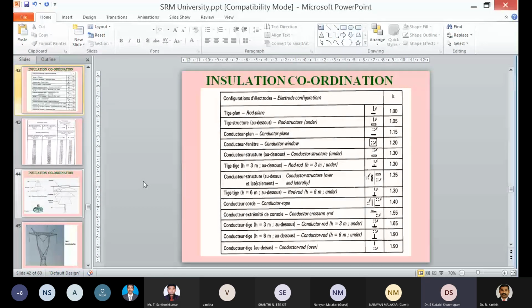So I have just shown an insulation configuration for calculation purposes. For a rod plane configuration, K is nothing but the factor by which we multiply. This is known as the safety factor in insulation design. In the next slide, I will explain, for different configurations, that is rod plane, rod conductor window, conductor plane, what safety factor we will consider. With respect to this factor, your insulation distance will vary.